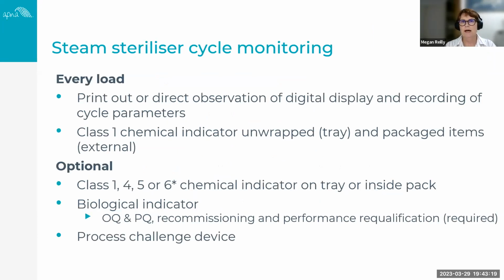So we look at the printout or direct observation of the display, and what we're doing is looking at the recording of those cycle parameters: temperature, pressure, and time. You look at the class 1 chemical indicator, which should be on every package, so it's external, or if you have an unwrapped tray, you should have a class 1 chemical indicator sitting on that.